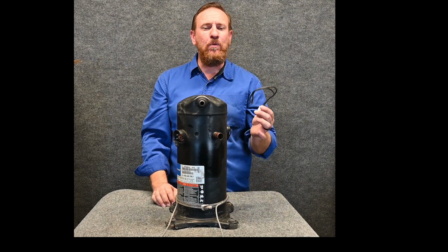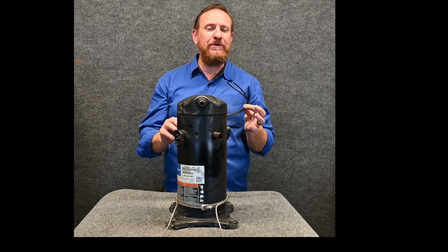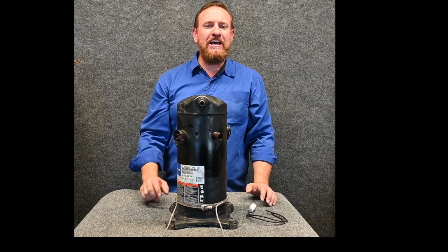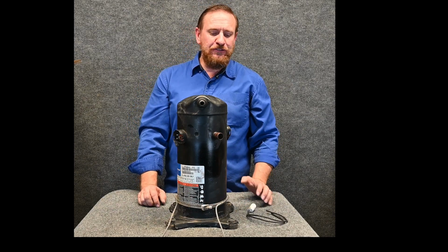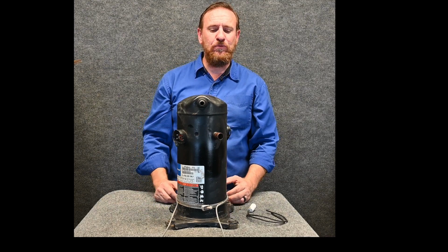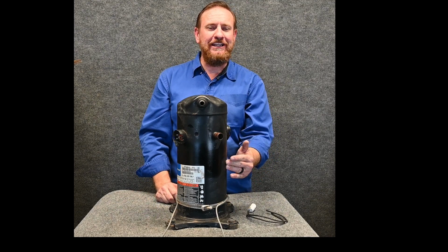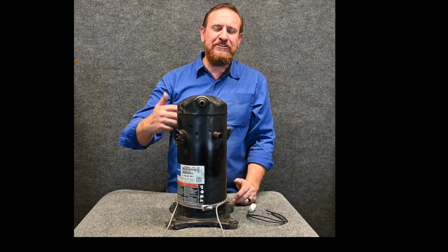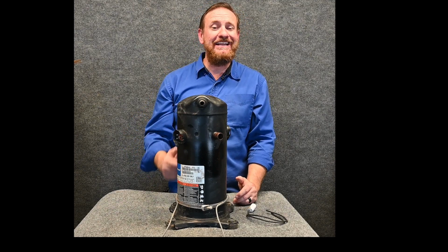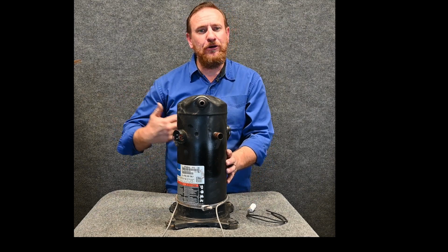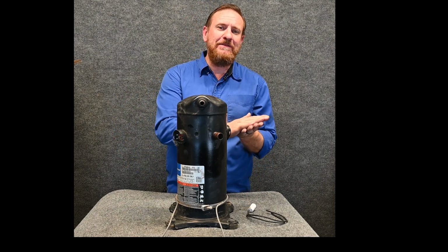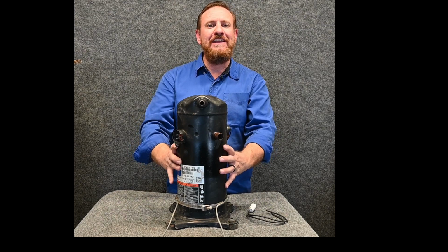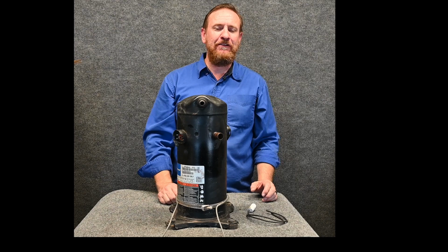We're going to talk about how to wire that and the many different ways of doing that later on when we get to electrical. Now there's yet another way of doing it. Some use a combination of this as well as powering the windings. When we talked about all those electrical windings inside the one that was cut open, we could actually send a small current through those windings. And it's not enough to make the motor run, but it's enough to create some heat. And we're actually using the windings inside that compressor to create enough heat to also help prevent refrigerant migration.